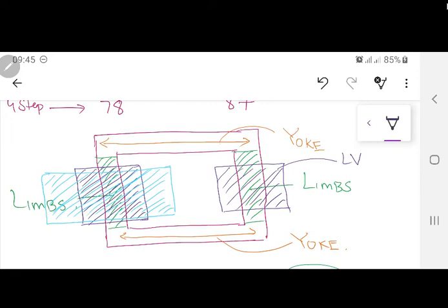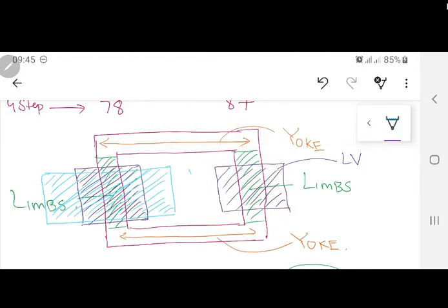This is very important in electrical engineering, or the course of high voltage engineering which you are going to do in the next semester. There is no such concept of an insulator. Every insulator still conducts. So similarly in a transformer, if I place a high voltage winding closer to the core, what will happen? Through the enamel, through some asbestos sheets, some current will flow over there. So by keeping the high voltage winding away from it, I am actually trying to reduce those partial discharges. So the high voltage winding I am going to place over here, like this one. So this is the high voltage winding which has been placed.